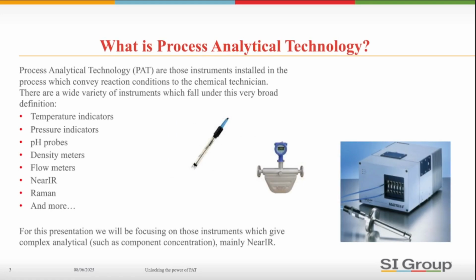So what is process analytical technology? Broadly speaking, it's any of the devices installed on process equipment which relate to the chemical or process conditions. Examples include thermocouples, pressure transducers, flow meters, and inline pH probes. However, for this discussion, we'll be focusing on those systems which relay complex analytical results, such as component concentration — more specifically, NIR.